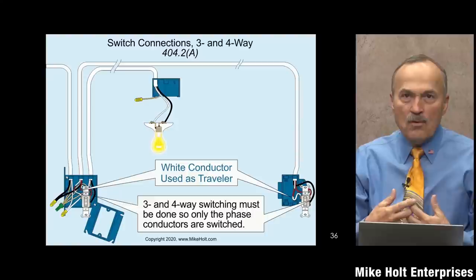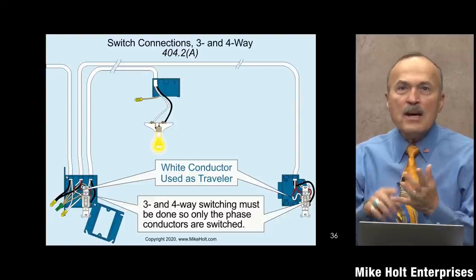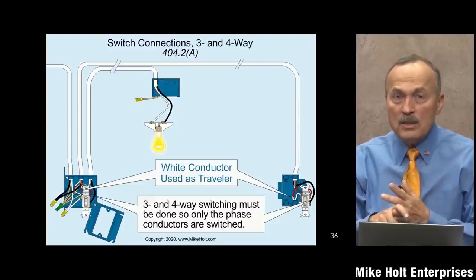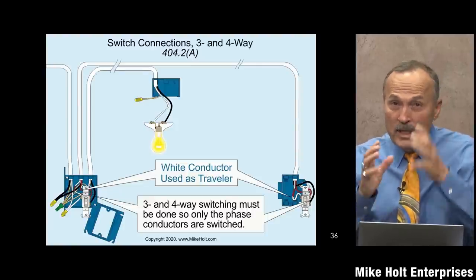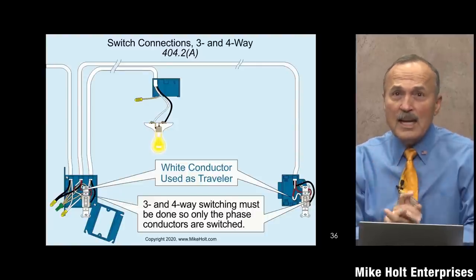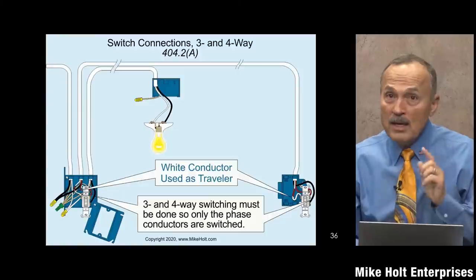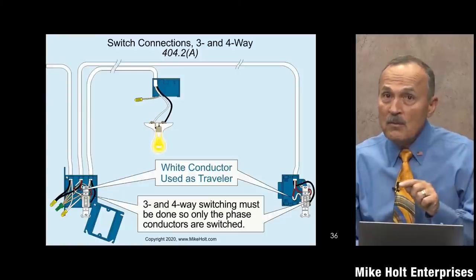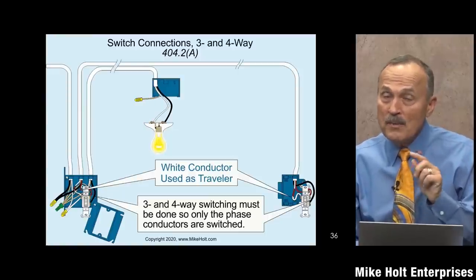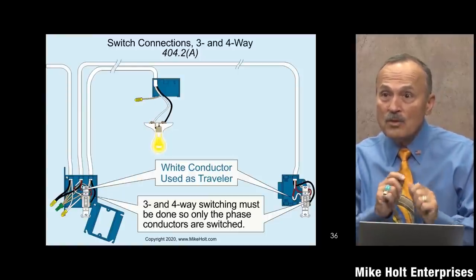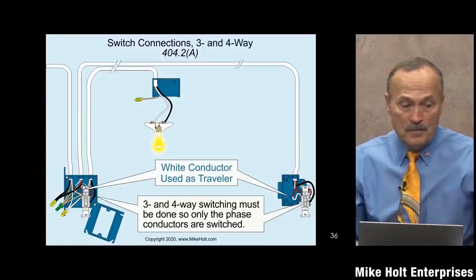Go on the internet — that's not part of this program — and learn about three-way and four-way switching. Study that so you can handle it. But here's the key: when you look at those graphics, make sure they are not showing the neutral conductor being switched in their demonstration.